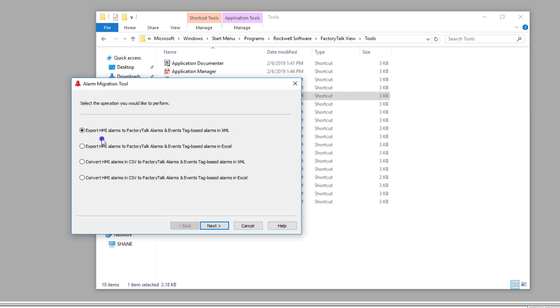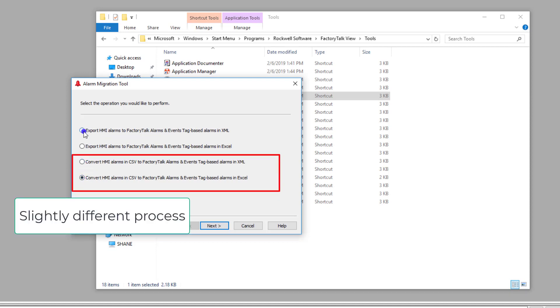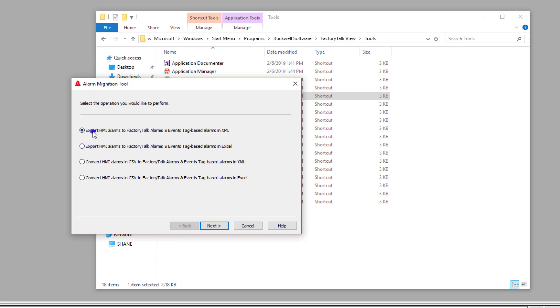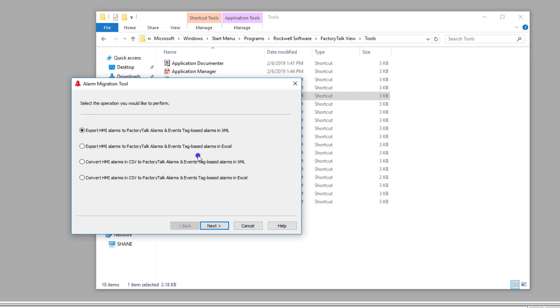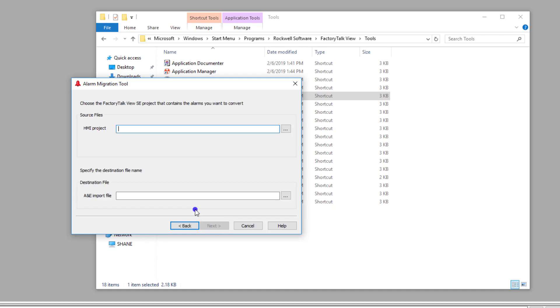There are a couple of instances here. If you've already converted or exported your HMI tags, you can utilize the two bottom methods. I'm going to show you how to do this if you haven't done that yet. The top two options are Export to XML or Export to Excel — we're going to use Excel. Both export HMI alarms to Factory Talk Alarms and Events tag-based alarms; you're just choosing whatever format you want to use.